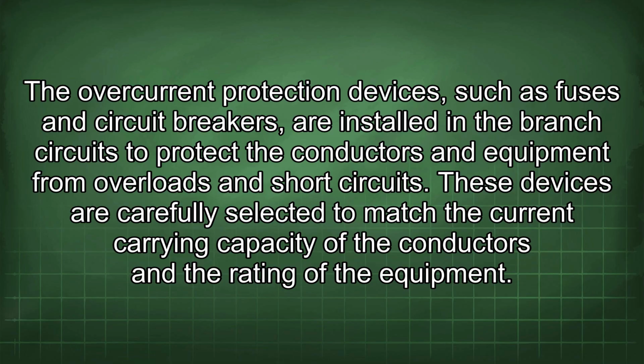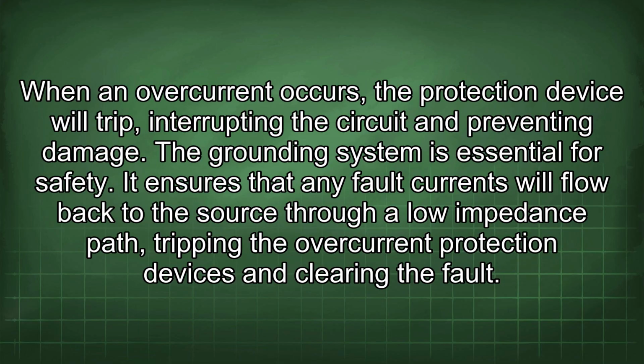The overcurrent protection devices, such as fuses and circuit breakers, are installed in the branch circuits to protect the conductors and equipment from overloads and short circuits. These devices are carefully selected to match the current carrying capacity of the conductors and the rating of the equipment. When an overcurrent occurs, the protection device will trip, interrupting the circuit and preventing damage. The grounding system is essential for safety. It ensures that any fault currents will flow back to the source through a low impedance path, tripping the overcurrent protection devices and clearing the fault.